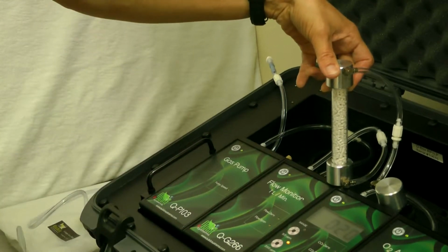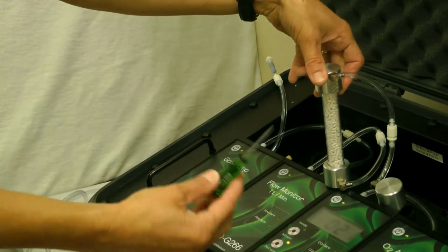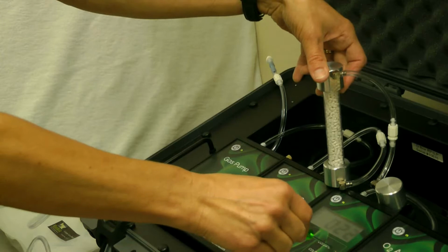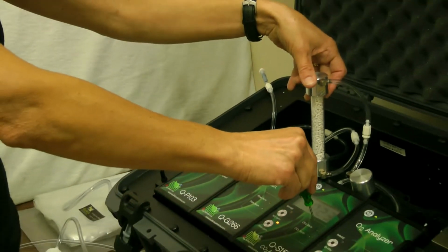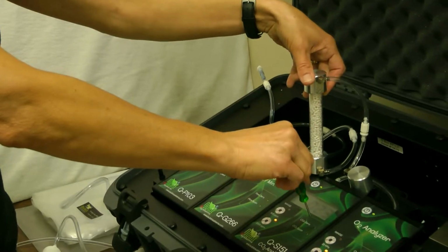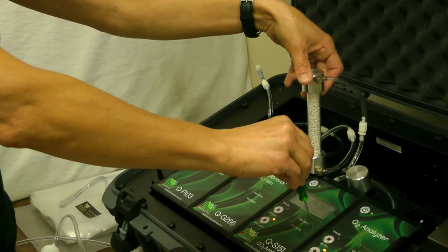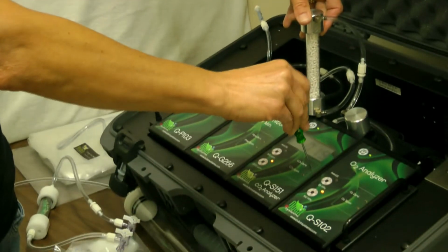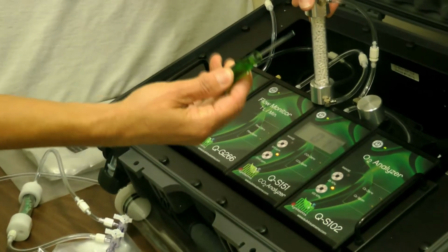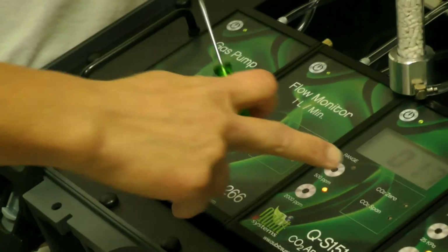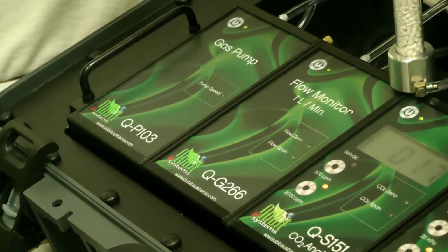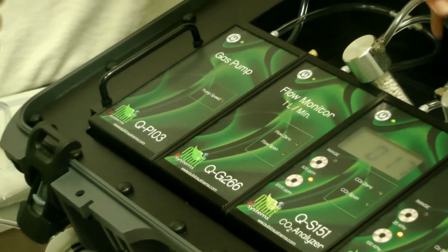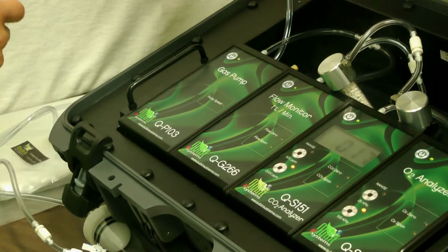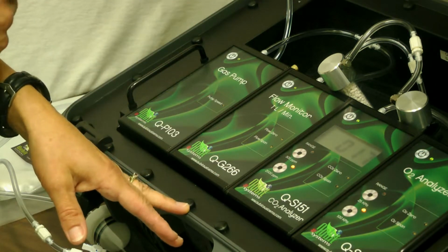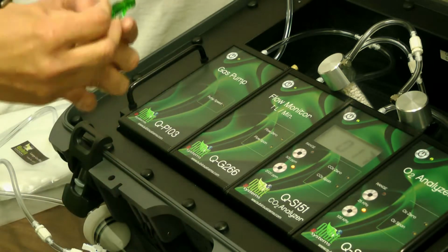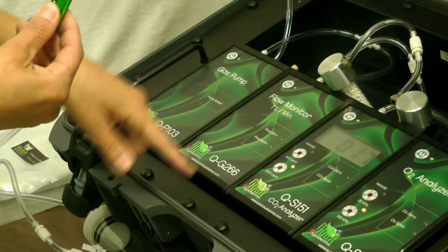If your 0 is not on the display exactly 0, you can adjust it using this little screwdriver by turning the potentiometer here in the counterclockwise direction to reduce and clockwise direction to increase the signal. So you would do that until you reach 0. If this value is quite high, this is a fine 0 control. You may have to go to a coarse 0 control, which is on the back of this instrument, and it's not visible right now, and it shouldn't be accessed unless it's absolutely required. And the manual explains how to adjust it. It's also a small screw that you use this screwdriver to adjust and reduce the 0.